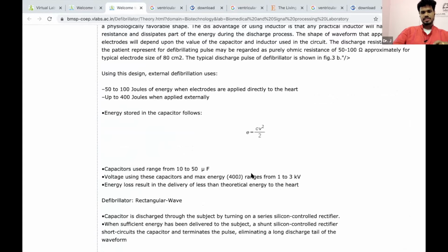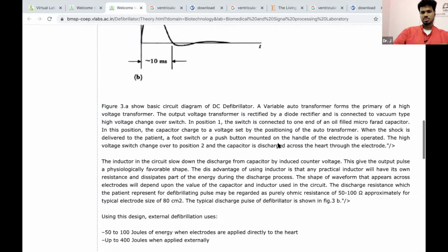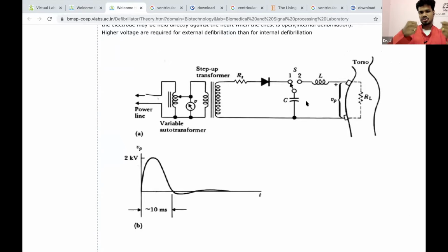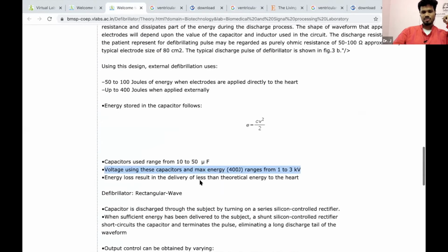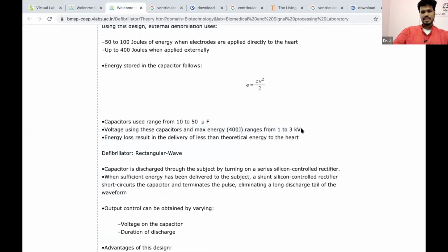One of the questions they are typically concerned about is the energy that needs to be stored in the capacitor for each charging, because this charging and discharging is important. Specifically, if you have the defibrillator within your heart, how long will the battery last? That is determined by how much energy a specific defibrillation pulse needs. So this calculation is very important. All it boils down to is energy is half CV squared, right? Capacitance, voltage squared, all that we know.